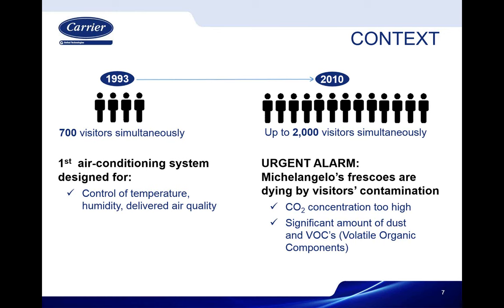The preservation of the frescoes matters because the plaster is calcium carbonate, and if you get moisture combined with a high concentration of CO2, you start forming carbonic acid, which dissolves the calcium carbonate. You end up with calcium bicarbonate dusting or white clouding on the surface, and that actually happened. There was some conservation done five years ago, and they said we've got to worry about that CO2. We were not concerned about it originally, so this is a change from the first designed system.